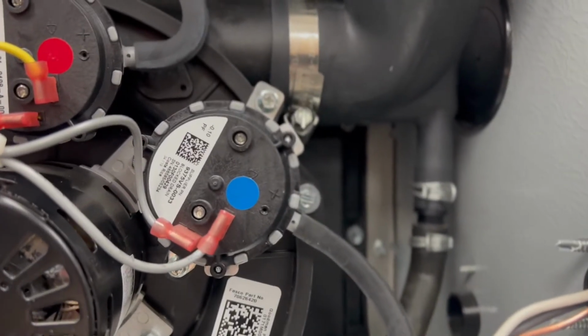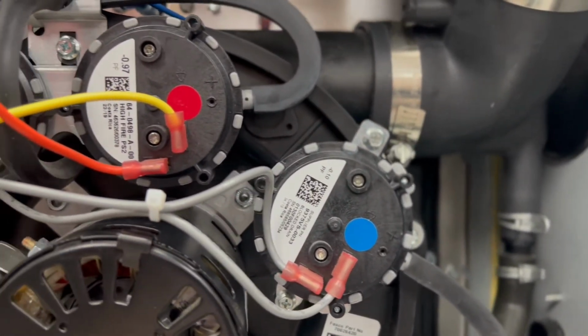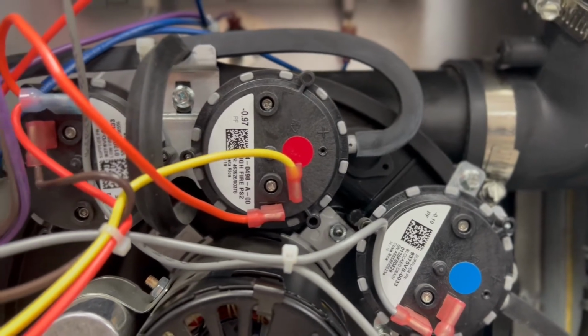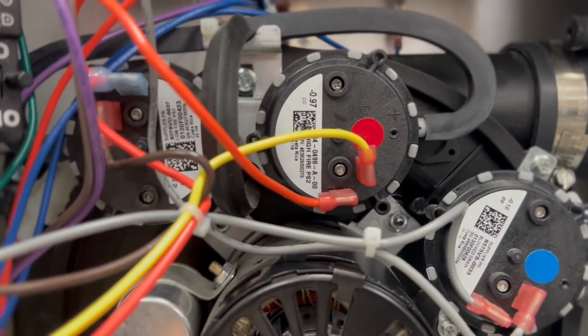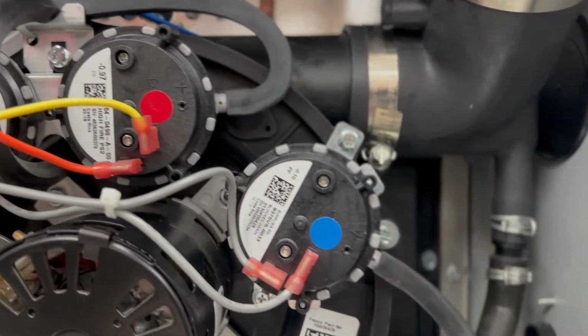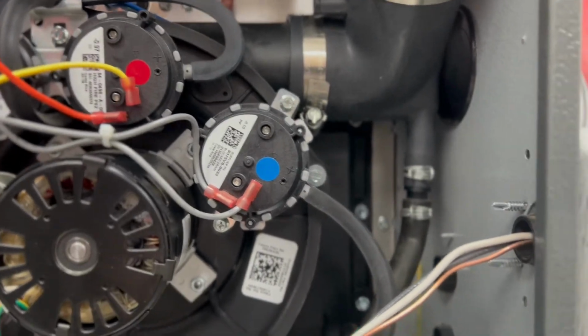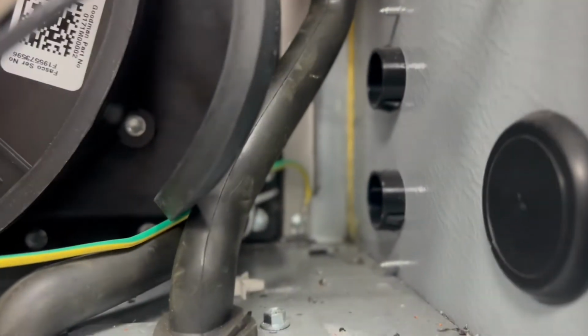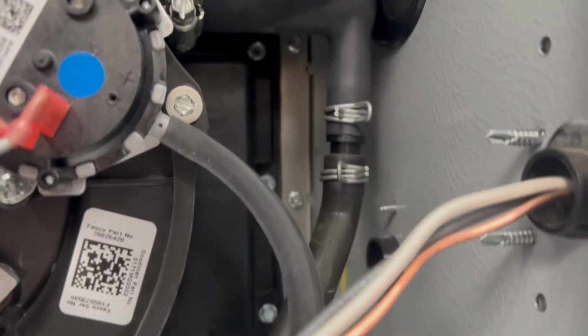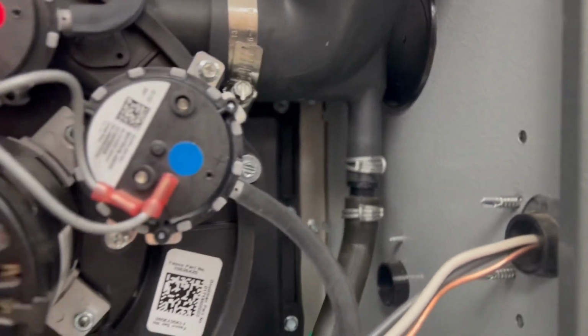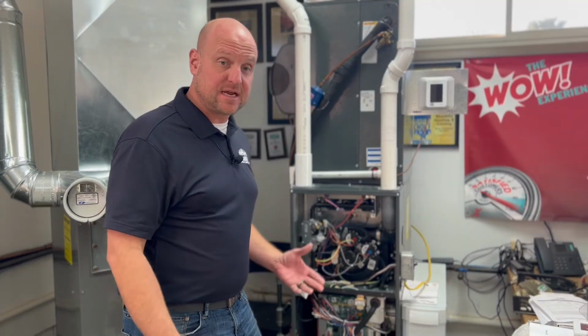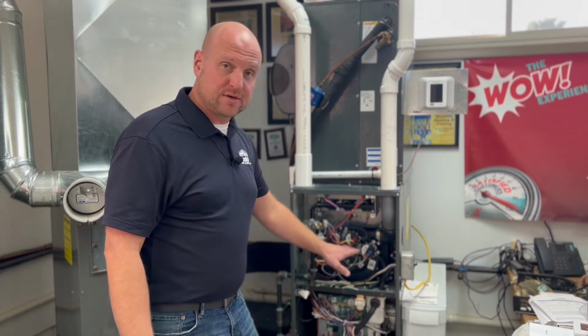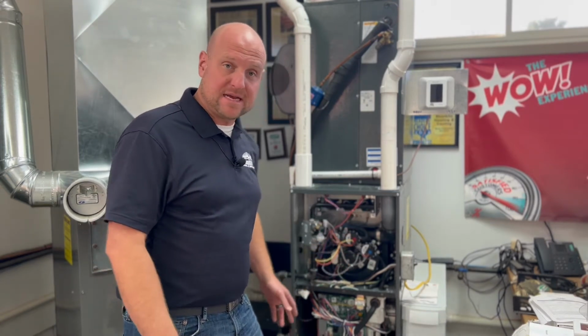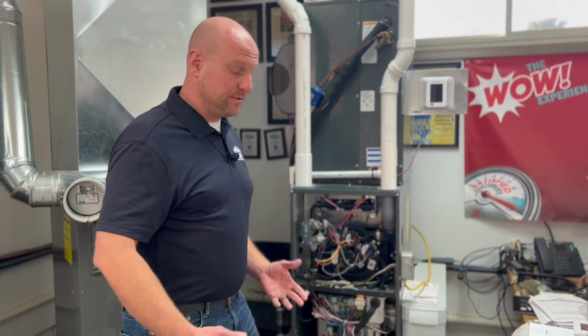They are actually measuring the vacuum on this draft inducer. This one happens to have 3 for the multi-stages of the furnace. Some of them just have 1. This is going to measure the vacuum of the draft inducer through this pressure tube. Once that is performed, the pressure switch is going to say, yes, I am okay, the draft inducer is working properly. It will send power back down to the circuit board to prove that.